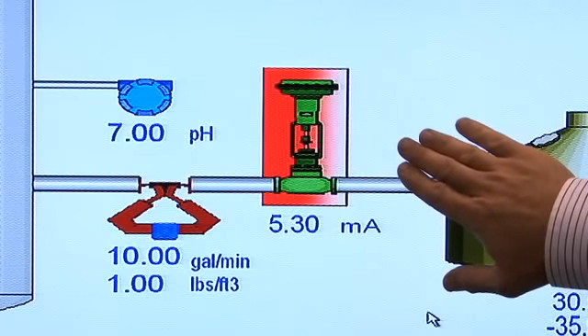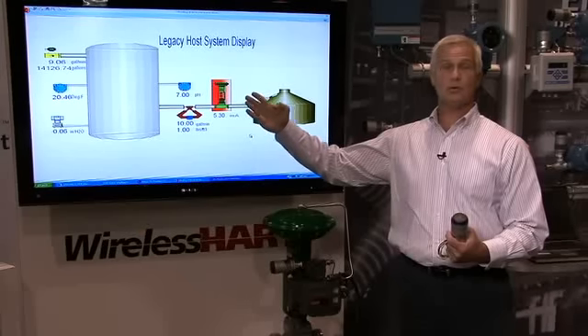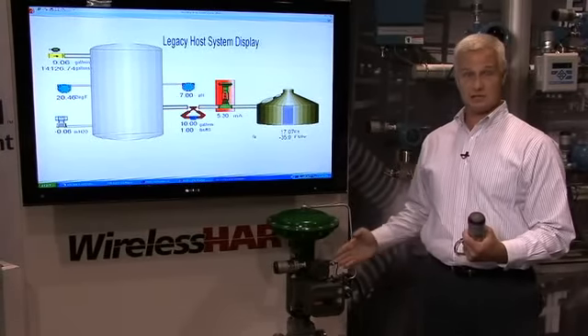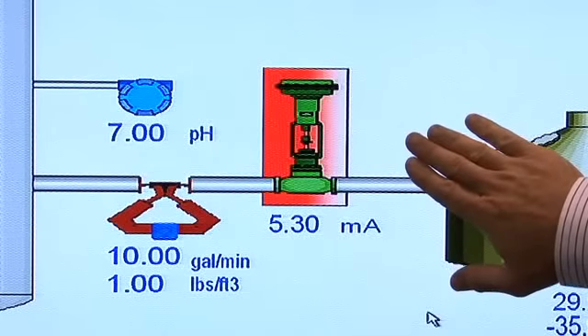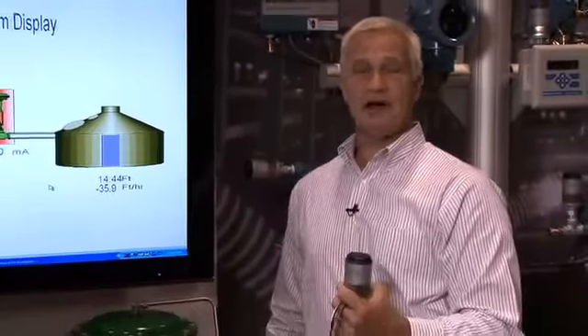From the display, you can see that even in your legacy system, it no longer has to be Ovation or Delta V, that we're able to pick up through OPC in this particular application the fact that we have an issue with the valve. So, using AMS, your technician would be able to diagnose the problem wirelessly before he ever goes to the valve.